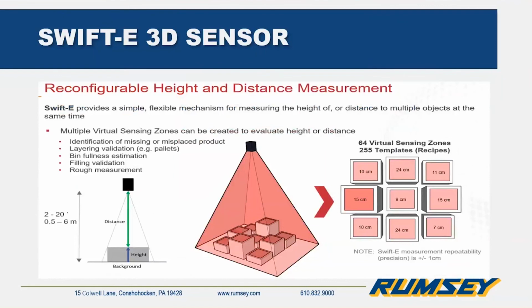The Swift-E is a 3D time of flight technology, which allows for reliable sensing and height measurement. So it's Ethernet compatible, with Studio 5000 add-on profiles. It can store up to 255 templates with 64 virtual sensing zones in each template. It's great for height and distance measurements, for robotic palletizing, where maybe the robot placed a box on there facing the wrong way. Also case packaging inspection, where you need to make sure that there's 6 items in a case and it'll sense that only 5 are in there and kick it out.